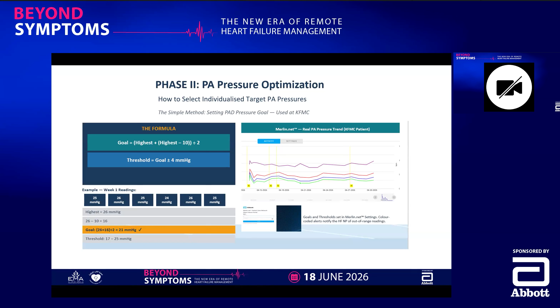In phase 3, what do we do when the pressure reading is high? First step is to confirm location. In this phase we are focusing on maintaining the patient's target PA pressure. When a high pressure reading is detected, we first confirm the patient's location, because moving to a city higher above sea level can increase the PA pressure reading. For example, a patient traveling from Riyadh city to Abha city may show an increase in PA pressure that is related to the change in elevation rather than worsening heart failure.